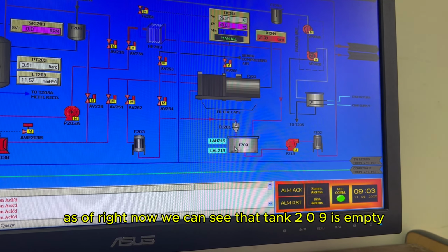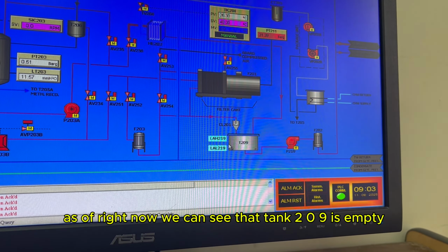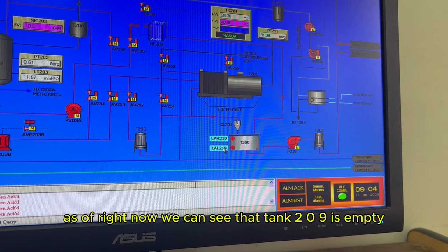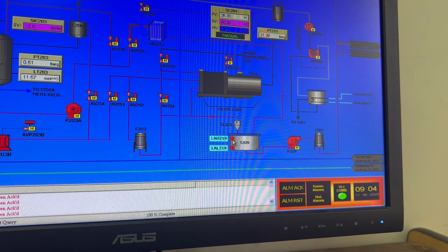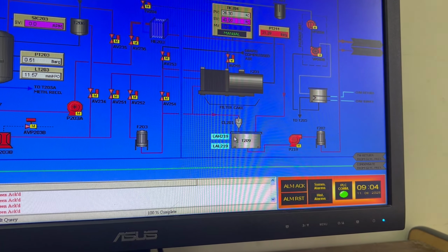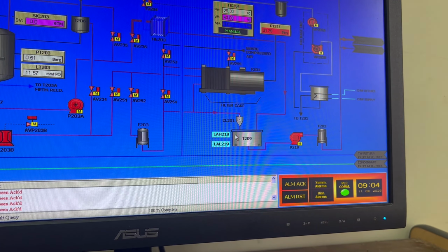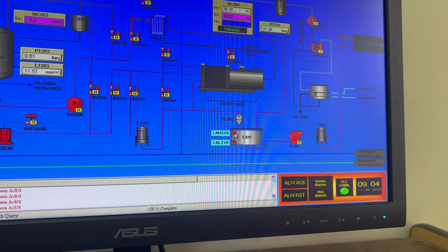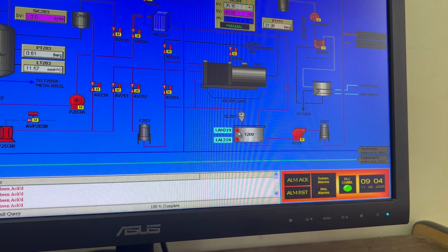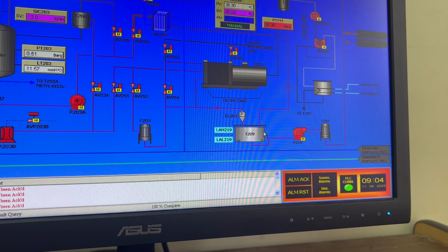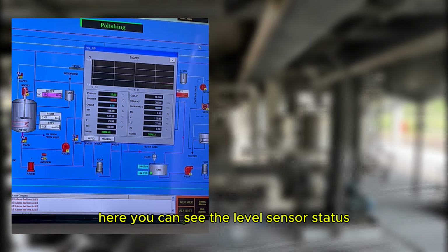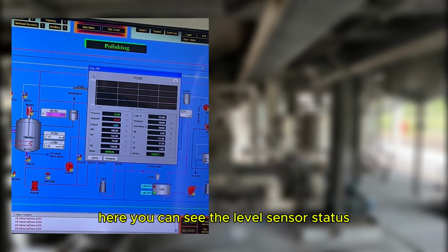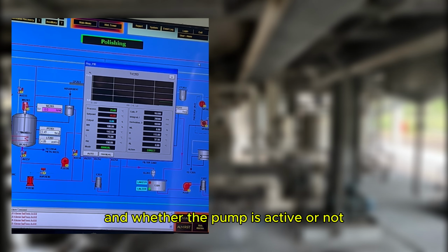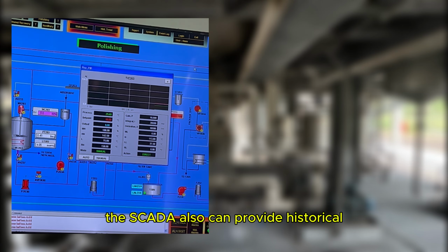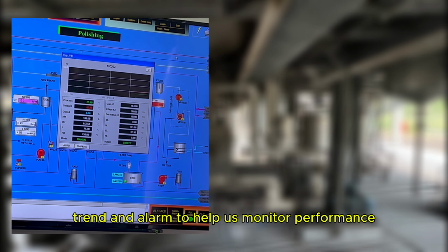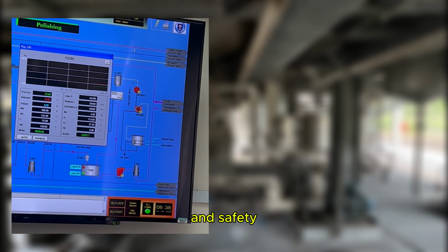As of right now, we can see that tank 209 is empty. Here, you can see the level sensor status and whether the pump is active or not. The SCADA can also provide historical trends and alarms to help us monitor performance and safety.